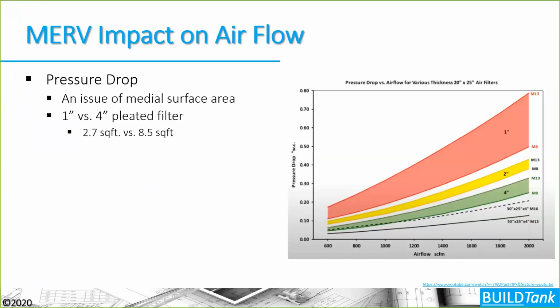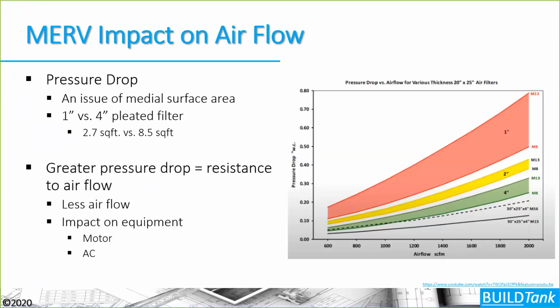This restriction of the flow of air is dictated by the pressure drop across that filter. And what we see from the difference between a 1-inch filter and a 4-inch filter is that the surface area of that filter is increased so much. In this case, we have 2.7 square feet for a 1-inch filter. When you go to a 4-inch pleated filter, they might both be the same rough size, being a 20 by 20 or 25 by 25 filter, but its surface area increases tremendously because it's a pleated filter. So we have 8.5 square feet. And you see that the pressure drop in the diagram to the right, for the 4-inch filter in green versus the 1-inch filter in red, is significantly less, just because of the greater surface area.